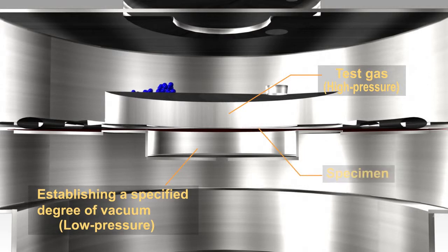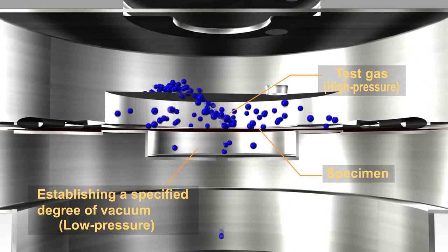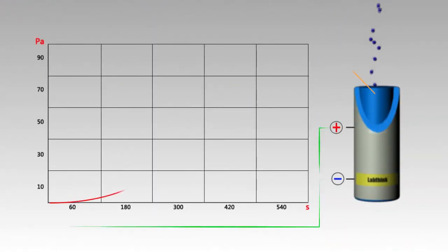The test gas then permeates from the high pressure chamber to the low pressure chamber under the gradient of differential pressure. Finally, the computer calculates the barrier properties of the test specimen by measuring the pressure change in the low pressure chamber.